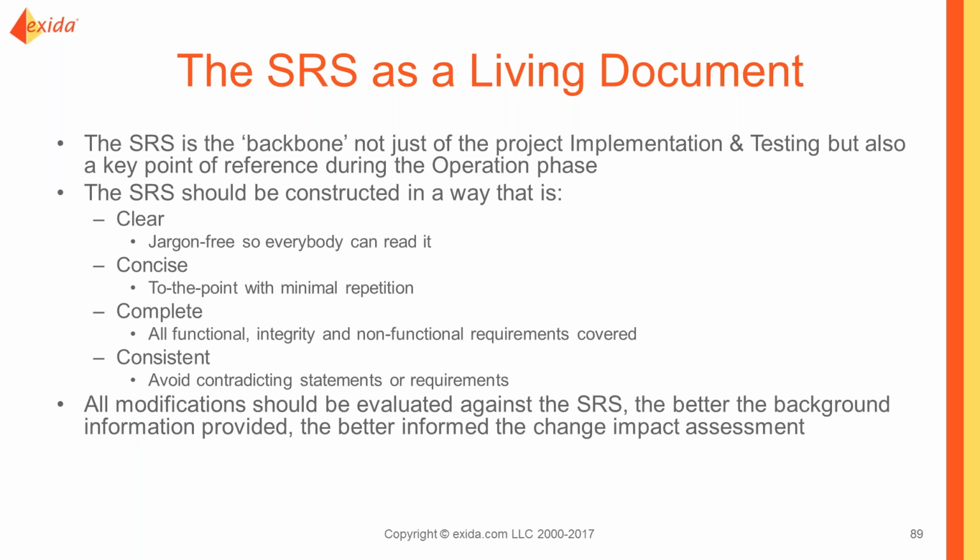So the SRS is a living document, needs to be maintained and updated over time, especially the first time through as you're designing the systems, because you may put concepts down when you first write the SRS, and when you do the design, you find a better way to do it, or you find that the original thoughts couldn't be achieved.